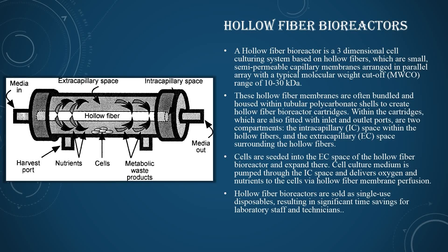The hollow fibers are bundled within tubular polycarbonate shells to create the hollow fiber bioreactor cartridge. Cells are seeded into the extracapillary (EC) space of the hollow fiber bioreactor. Cell culture medium is pumped through the intracapillary (IC) spaces, delivering oxygen and nutrients to the cells via the hollow fiber membrane. Hollow fiber bioreactors are sold as single-use, resulting in significant time savings for laboratory staff and technicians.